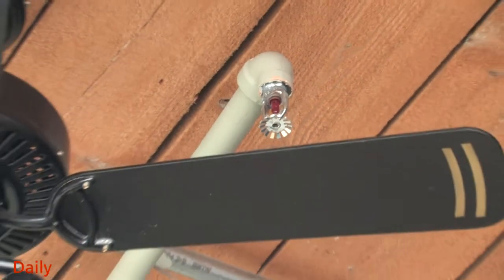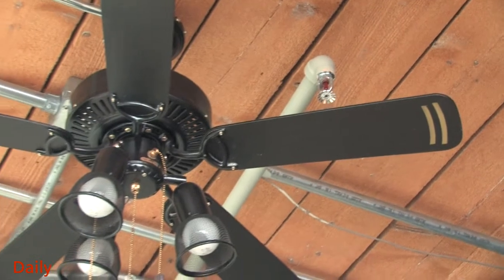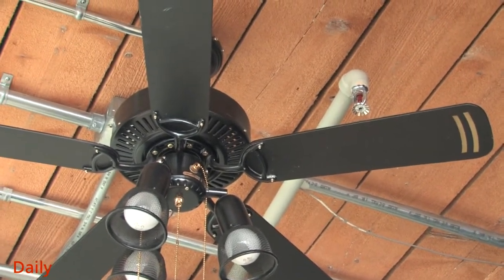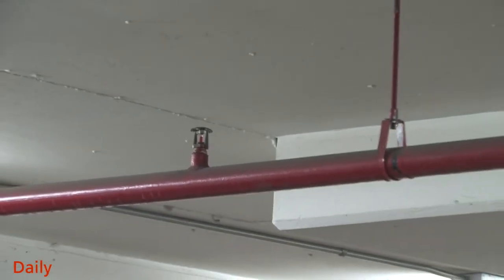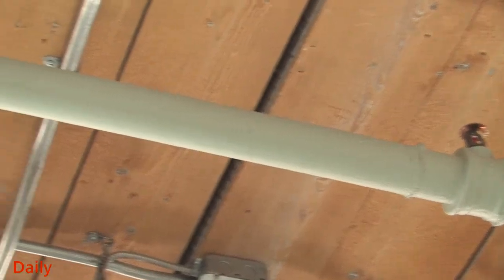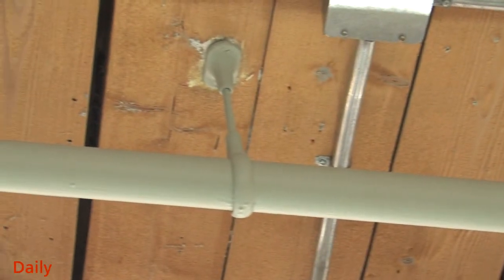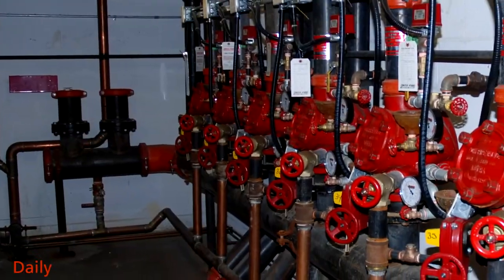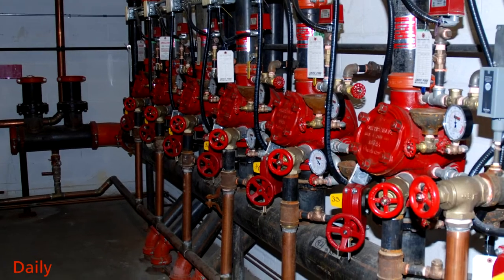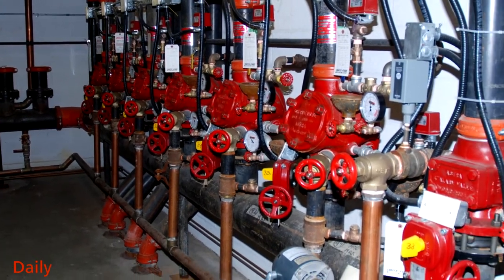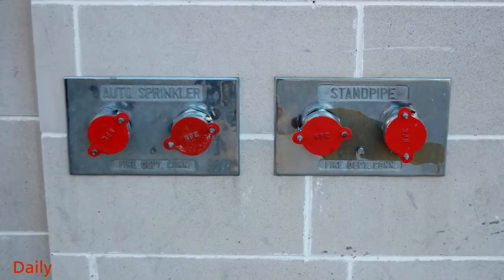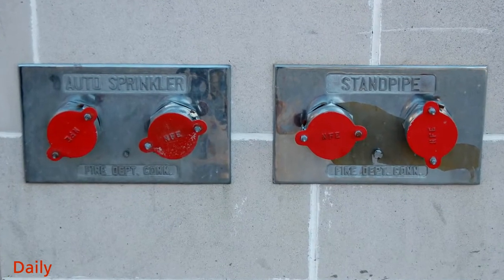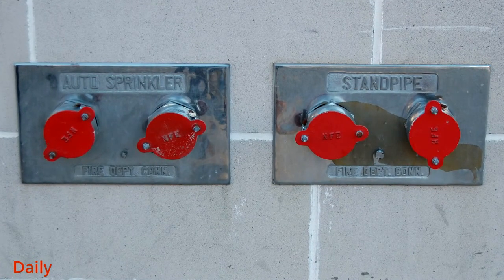There must be no obstructions around sprinkler heads that might interfere with their water discharge pattern. Sprinkler systems and their piping networks must not be used to support anything that will interfere with sprinkler performance, and sprinkler piping and hangers must be kept in good repair. Sprinkler control valves must always be kept accessible and maintained in operating condition. Exterior fire department connections must be equipped with plugs or caps and secured wrench tight at all times.